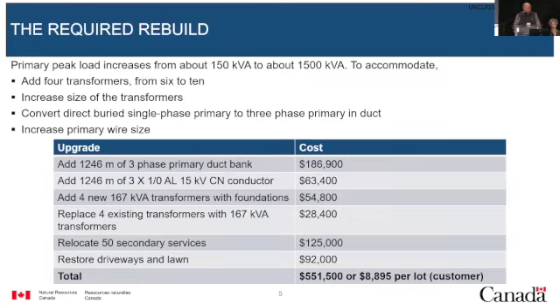What does that look like? The peak load on these 62 homes increases from about 150 kVA to around 1,500 kVA. To accommodate that, we add 4 transformers, increase transformer size, convert direct buried single-phase primary to 3-phase in duct, and increase primary wire size. The cost would be about $9,000 a lot.